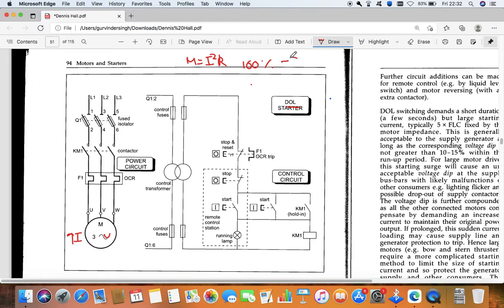Now, why are we using the DOL starter? The first thing is that it is simple and inexpensive. The initial cost is very low, and the maintenance is also less. These are the advantages of the DOL starter. We can also put in many safeties like the OCR, the overcurrent relay. We can control start and stop of the motor from remote, and also locally. If the motor is coupled with a pump, we can start and stop it with the help of a level gauge. So various safeties and controls can be put on the DOL starter.